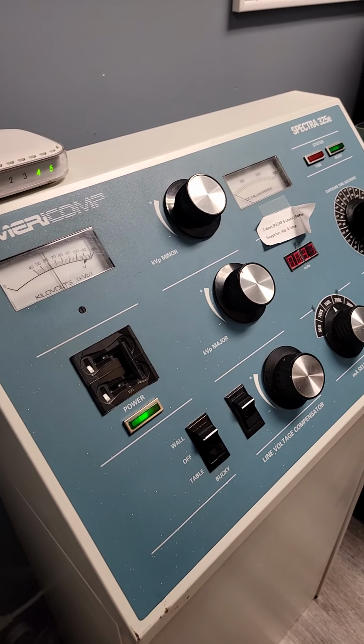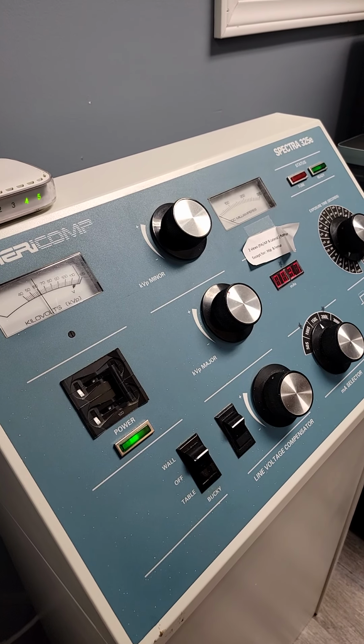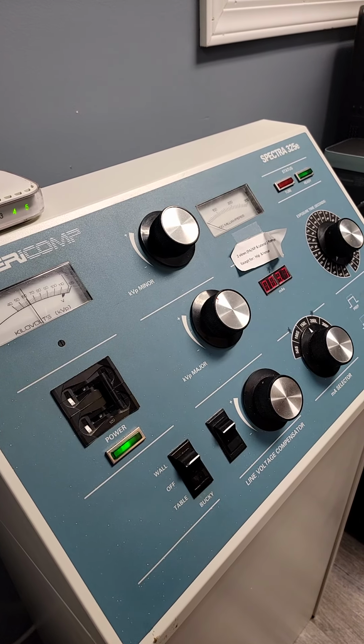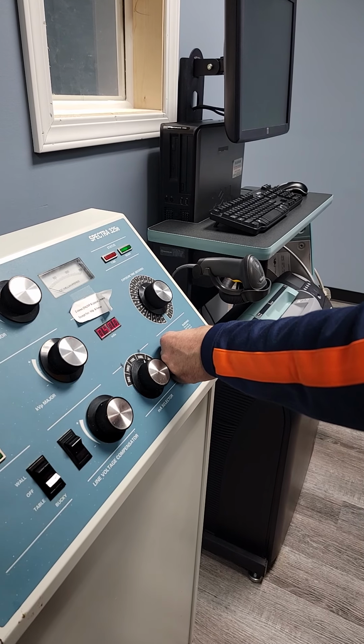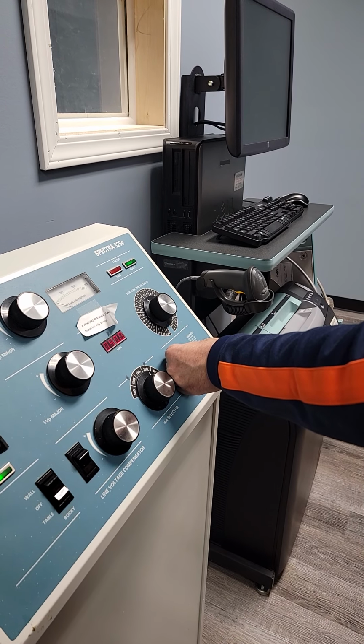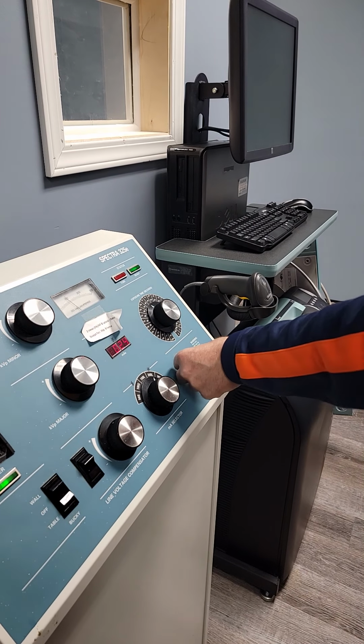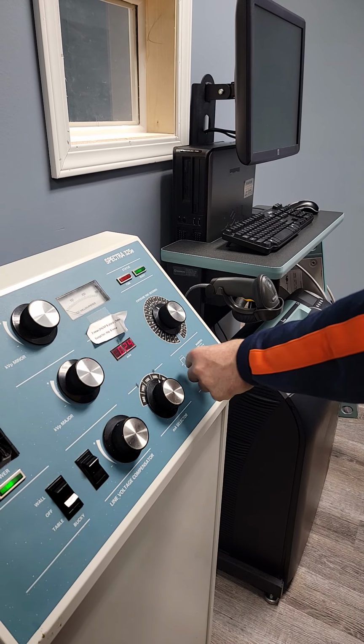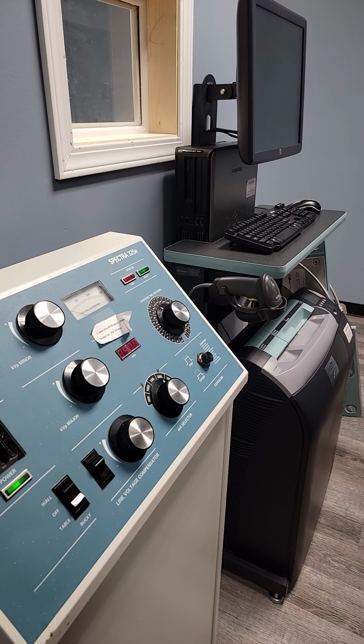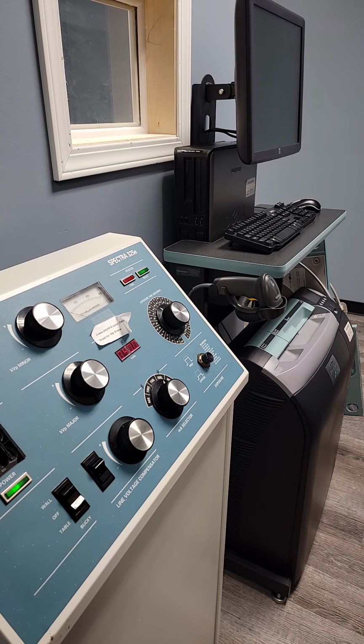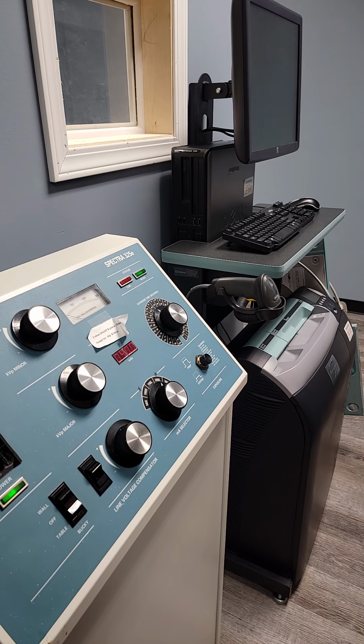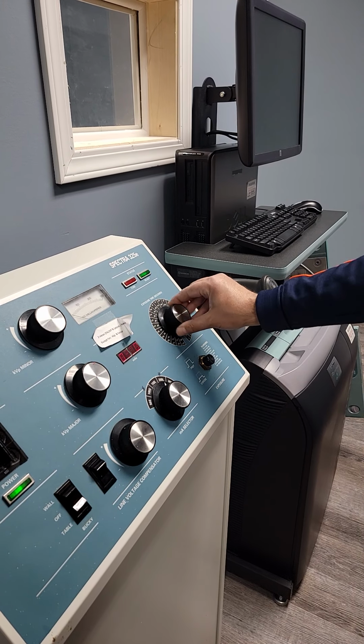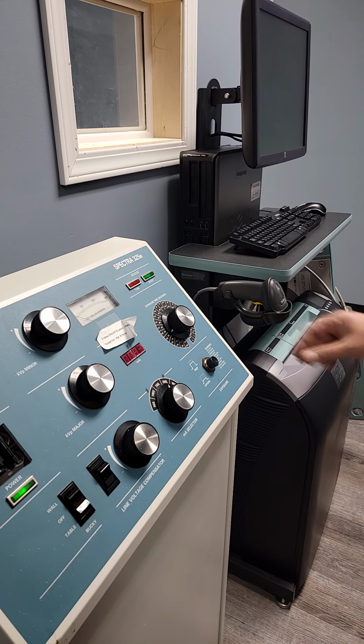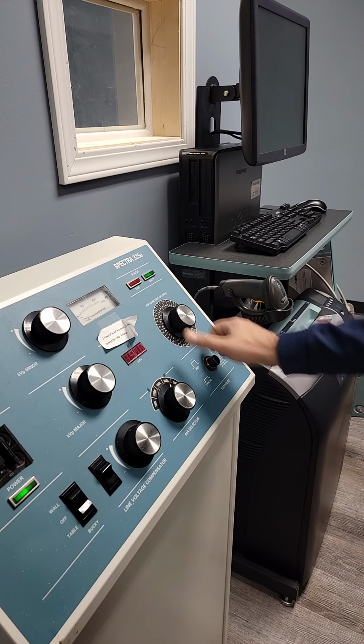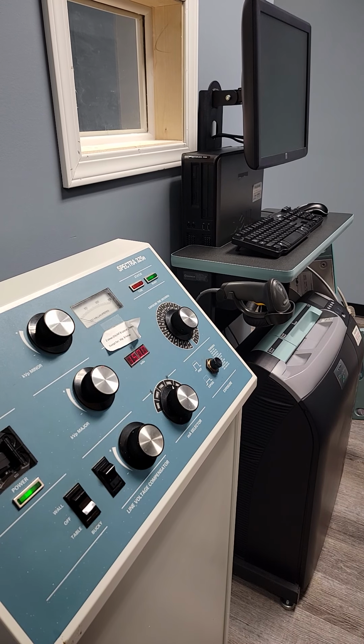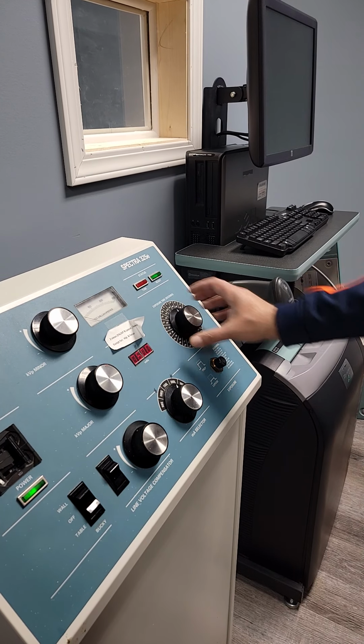It's just a good thing to do, because if it gets too far off, the machine won't even shoot an X-ray. Your light will go halfway to prep it. You hear the click, it's ready. John, are you out of the way? Then hold it all the way through till the beep is over, because if you let off, you terminate your exposure early and your film could possibly be light. That really doesn't come into play when you're shooting a 1/24th of a second X-ray, but when you get into a half or 3/4, it could, in theory, terminate and give you light films.